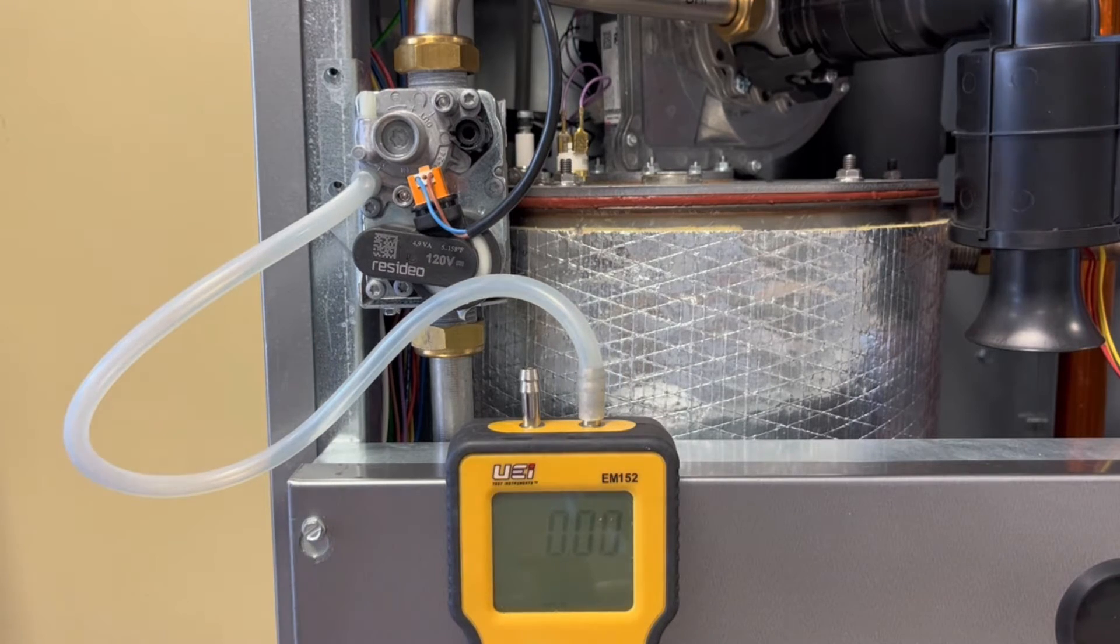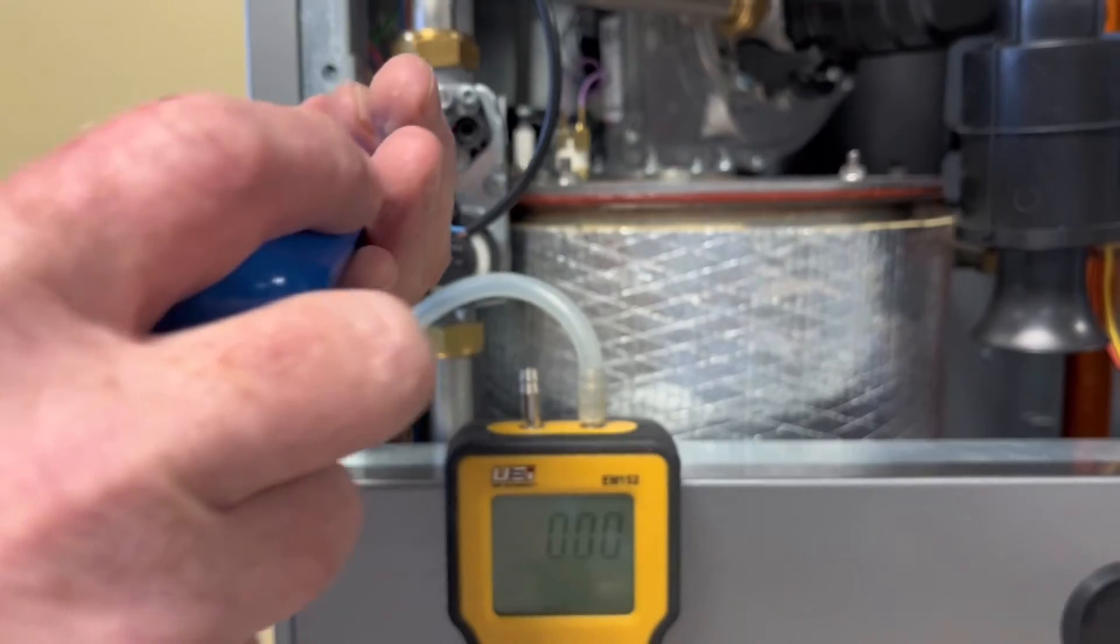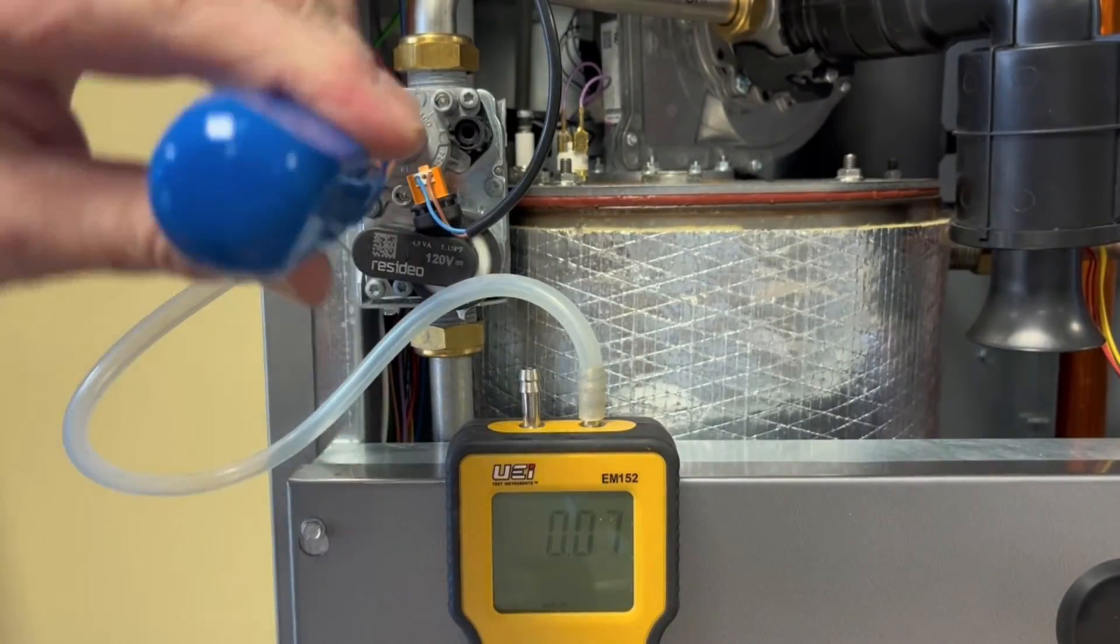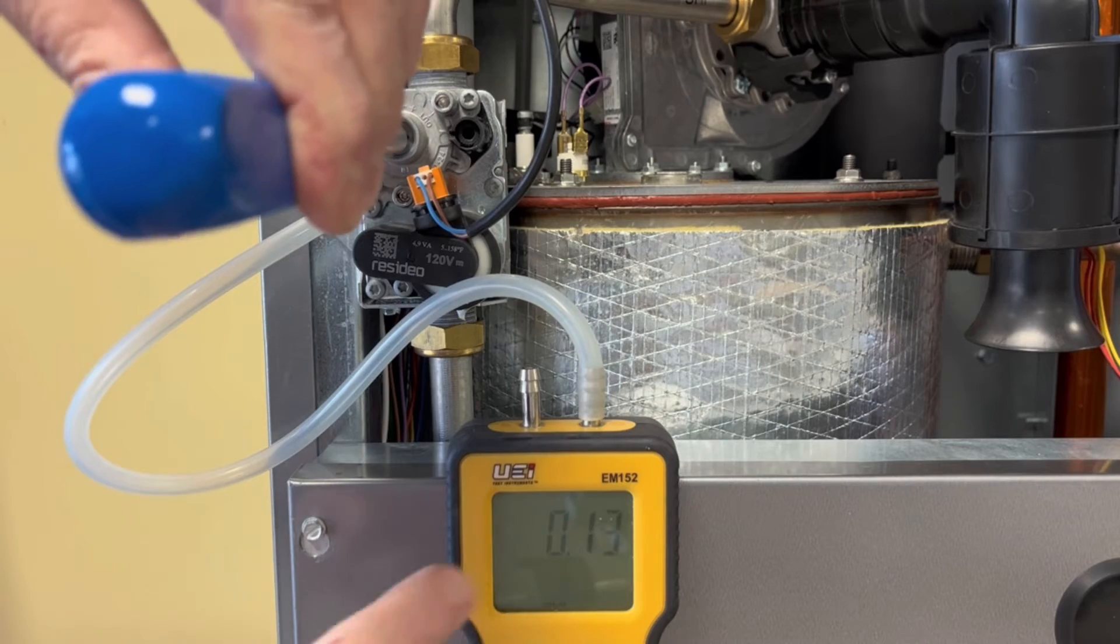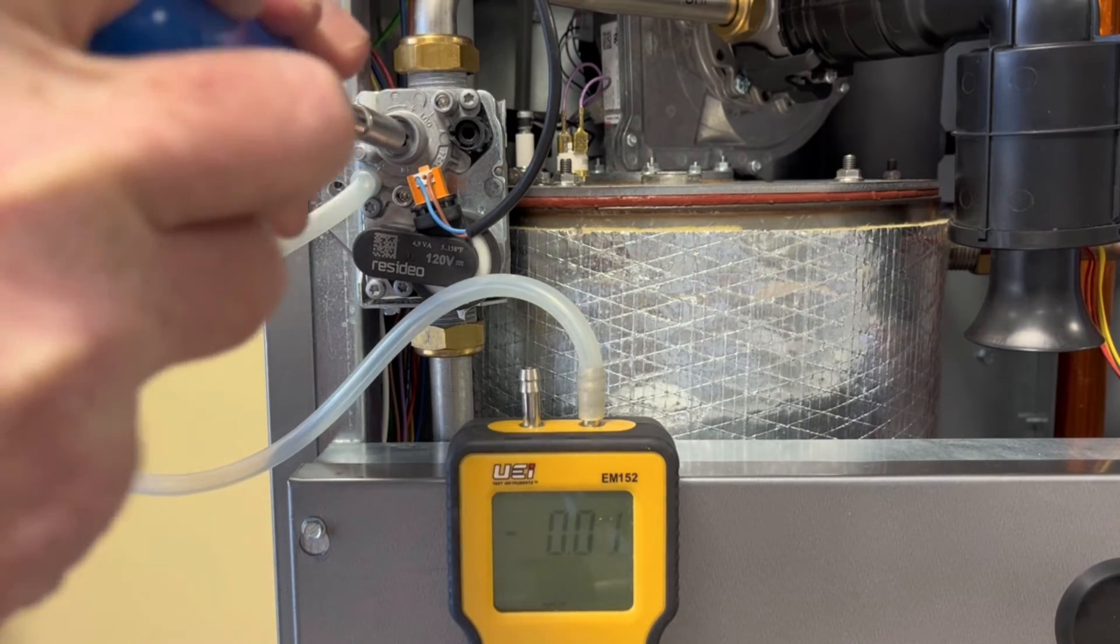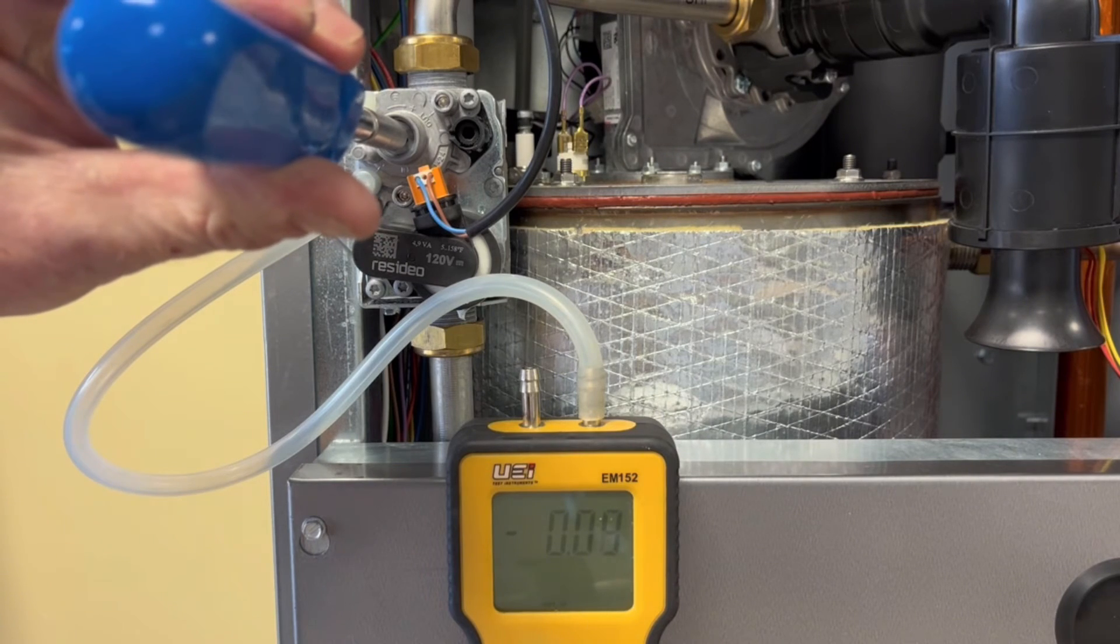On this valve, the pressure is already reading zero, but you'll notice that as I increase the gas flow, the pressure will go positive and become a bigger number. This is by turning the screw clockwise. If I decrease the gas flow by turning counterclockwise, the number will become negative.